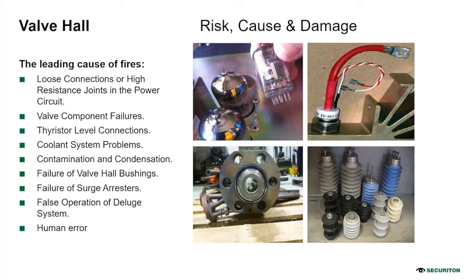Then you have failure of valve hall bushings. There are a lot of bushings there. High voltage bushings are basically supported through the walls of the valve hall, and these bushings allow connections between the converter transformer on one side and the DC switch yard on the other side. So you can see the chances of fire are always present here, even if you are using the right system.